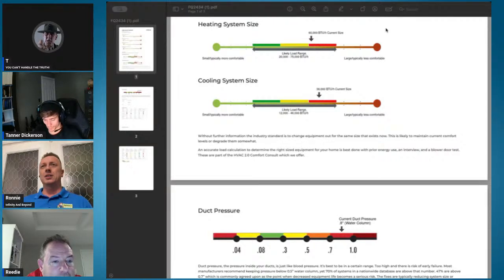He's not using the process, so you guys are totally exposed. He did a manual J load, and he looked at the house, and he looked at the ductwork, and he actually called me and said, Ronnie, I got this size ductwork, this size ductwork. That's a 3-ton duct system.